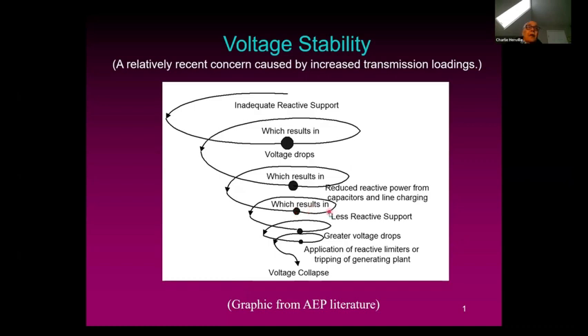Often it's not enough, and particularly capacitors and line charging capacitance will give less reactive power as the voltage drops. So the voltage drops even further, we have less reactive support, and eventually the generators can't supply any more reactive power. They have limiters that prevent them from doing this. And sometimes those limiters don't coordinate properly with the protection. And then the generators trip offline unexpectedly and panic and chaos result.